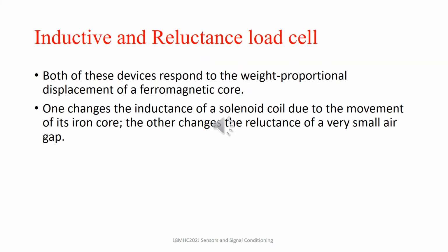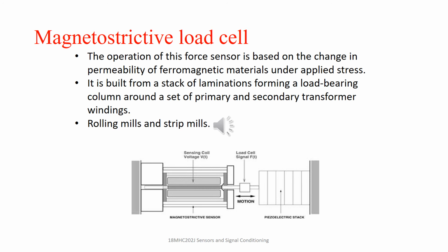Next type is the inductive and reluctance load cell. Both of these devices respond to the weight. Due to the movement of an iron core, the inductance of a solenoid coil changes and the reluctance varies across a small air gap. This is the magnetostrictive load cell.